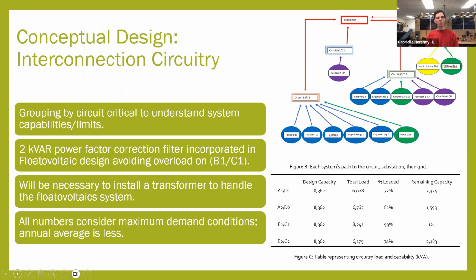We decided this was the first important step to develop within our means while building our designs. As you can see with circuit B1C1, our floatovoltaic would have overwhelmed the circuit had it not been designed carefully. To overcome this and prepare for future concerns, we installed a 2 kVAR power factor correction filter, which we recommend to avoid overload for future development.